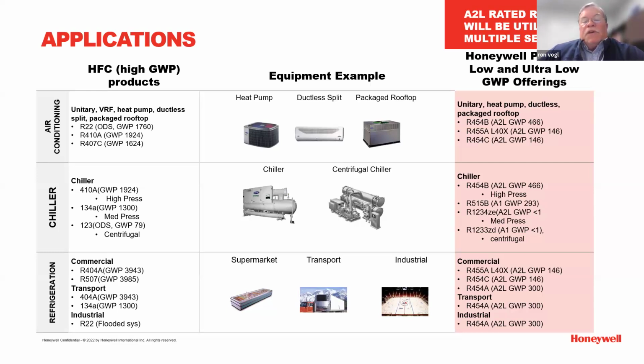In fact, you look at these chillers and you think air conditioning. We did a job over in Europe, a cold storage using a chiller, and the compressors were able to deliver 14-degree Fahrenheit glycol, which is sufficient enough to do a medium temperature cold storage. So not good for companies like Honeywell because chillers don't use a lot of refrigerant, but if you think of it, good for the environment, less than one, nicely built chiller. The economics of the project were great, and the performance has been excellent. So you're going to start seeing some innovative uses of refrigerants that you wouldn't have thought into the refrigeration market through the use of chillers and the rest of it.